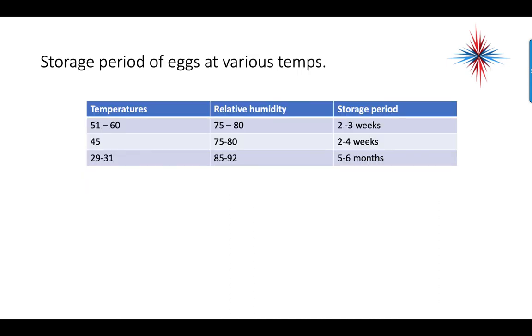Storage periods for eggs at various temperatures are as follows: 51 to 60 degrees with 75 to 80 percent relative humidity, 2 to 3 weeks; 45 degrees with 75 to 80 percent relative humidity, 2 to 4 weeks; 29 to 31 degrees with 85 to 92 percent relative humidity, 5 to 6 months.